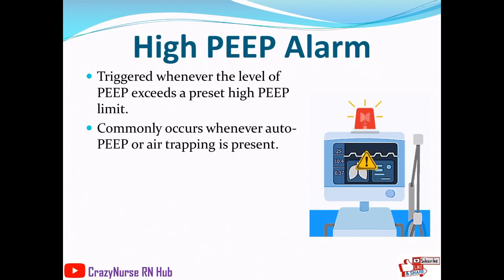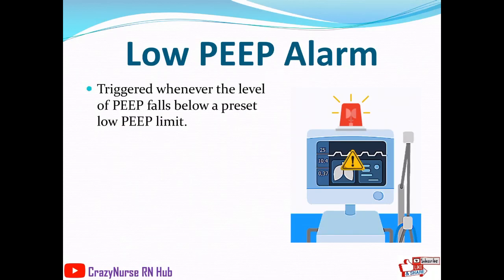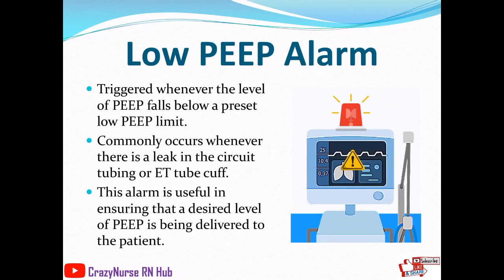The high-PEEP alarm is triggered when PEEP exceeds a preset high limit, common when auto-PEEP or air trapping is present. Auto-PEEP occurs when positive pressure remains in the alveoli at end-exhalation, increasing the work of breathing, but it can be reduced by prolonging expiratory time. The low-PEEP alarm is triggered when PEEP falls below a preset low limit, common with a leak in the circuit tubing or ET tube cuff, and is useful in ensuring the desired PEEP level is being delivered.